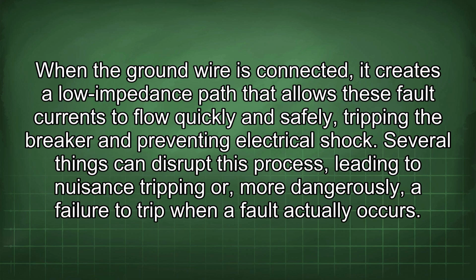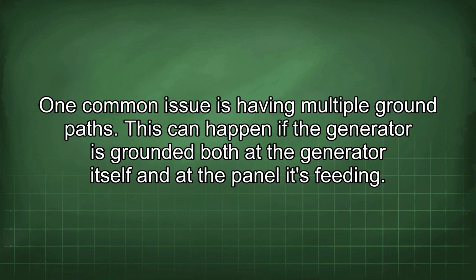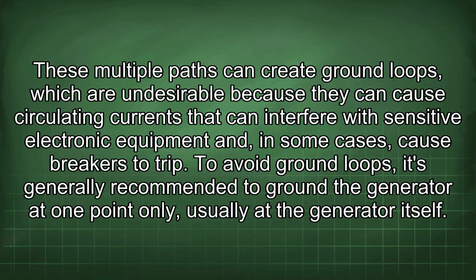Several things can disrupt this process, leading to nuisance tripping or, more dangerously, a failure to trip when a fault actually occurs. One common issue is having multiple ground paths. This can happen if the generator is grounded both at the generator itself and at the panel it is feeding. These multiple paths can create ground loops, which are undesirable because they can cause circulating currents that can interfere with sensitive electronic equipment and, in some cases, cause breakers to trip.